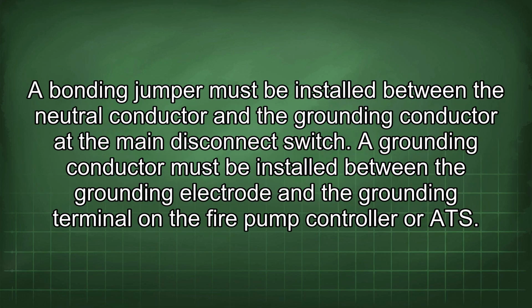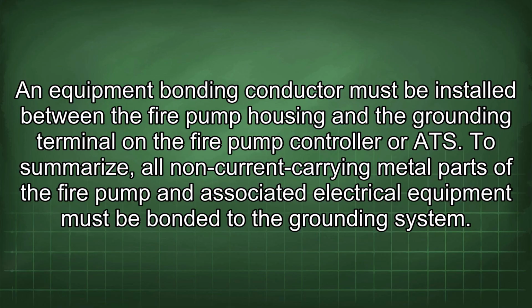A bonding jumper must be installed between the neutral conductor and the grounding conductor at the main disconnect switch. A grounding conductor must be installed between the grounding electrode and the grounding terminal on the fire pump controller or ATS. An equipment bonding conductor must be installed between the fire pump housing and the grounding terminal on the fire pump controller or ATS. To summarize, all non-current carrying metal parts of the fire pump and associated electrical equipment must be bonded to the grounding system.